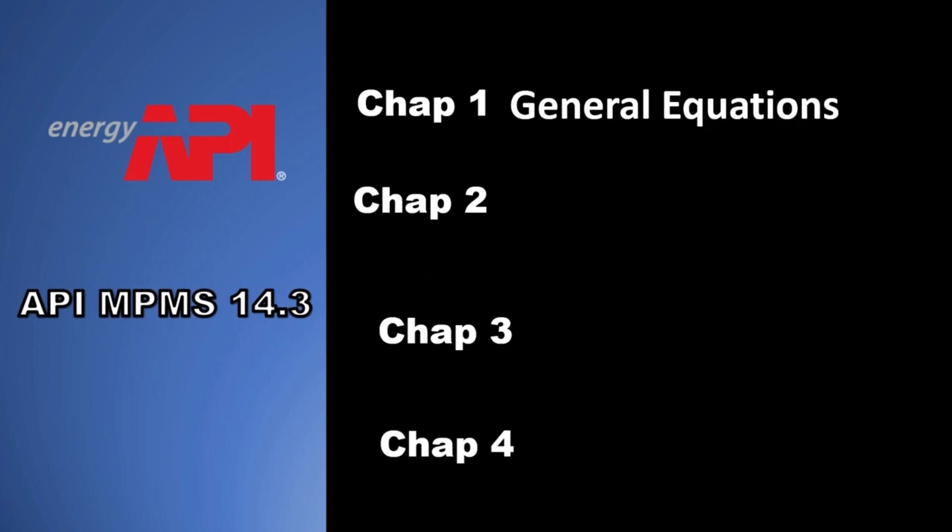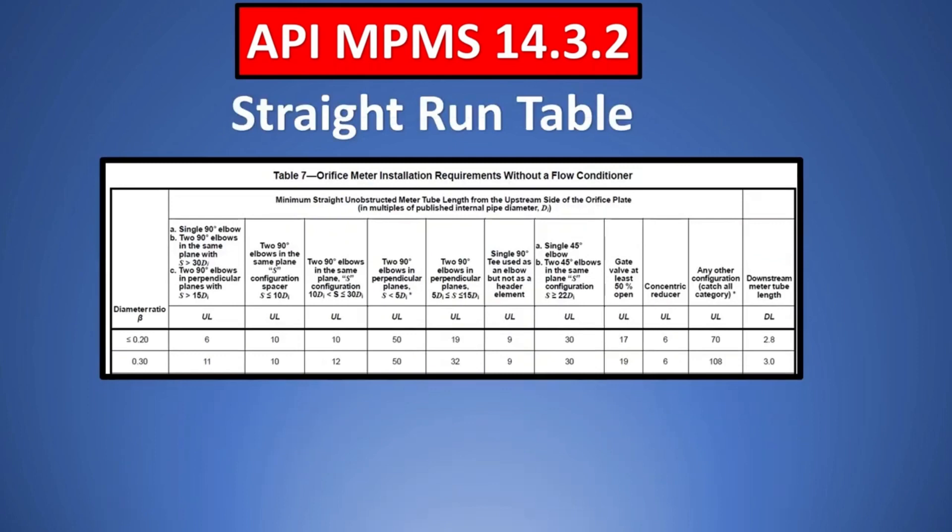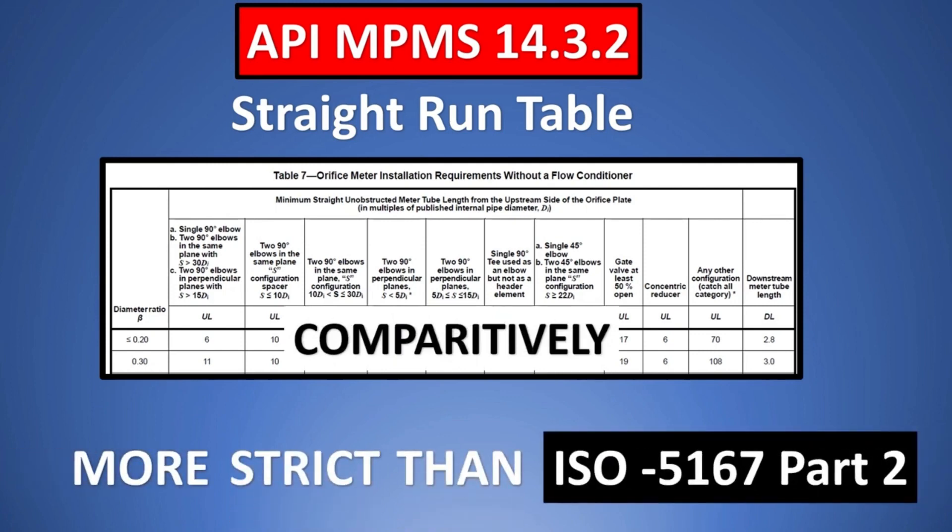The first one stands for general equations. One thing to remember here is all of these 4 deal with orifice plates only. The second one deals with the specifications which is the most important out of the 4. The third one basically deals with application of chapters 1, 2 and 4. And finally, the fourth one deals with what was the background, how was this developed, etc. So let us look into this chapter 2 which is specifications. Similar to your ISO standard, API MPMS 14.3.2 also has a straight run table. And it is very similar to ISO 5167 but comparatively, if you see, this is more strict than ISO 5167. Why? Because if you see the word MPMS here, it stands for manual of petroleum measurement standards. Because the petroleum products are more costly, hazardous, etc., the more stricter ways are used. So more straight run requirements etc. are defined here.